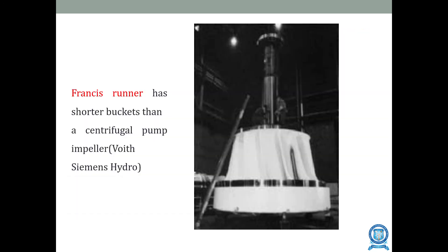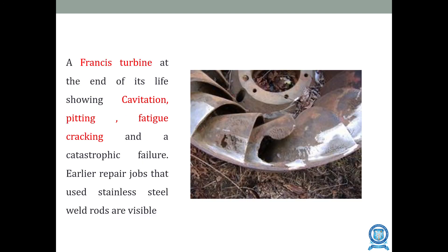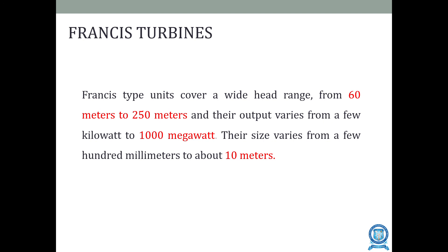The Francis turbine has short buckets compared with centrifugal pumps. A Francis turbine at the end of its life can show cavitation pitting, fatigue cracking, and catastrophic failure; earlier repair jobs using stainless steel weld rods are also visible. The diagram shows distortion due to cavitation pitting and fatigue cracking. The Francis turbine can handle heads from 60 to 250 meters, output ranging from a few kilowatts to 1000 megawatts, and runner sizes from a few hundred millimeters to about 10 meters.